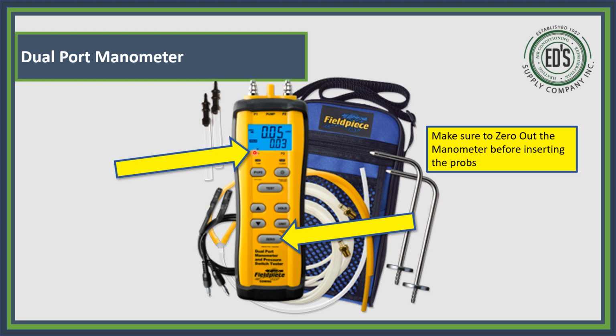Now, if I'm looking at P1 and I see my reading, if I see a 3 on my P1, I know I have resistance in my return. I should not see a 3 on return. I should see numbers 2, 1, or less. On my supply, which would be P2, I want to see numbers that may be 3, 4, and 5. If I see a 6, I've got restriction in my supply. If I see a 5, I've got restriction on my supply. So you can look at that real close and see where my problem is. Is it on the supply or is it on the return?